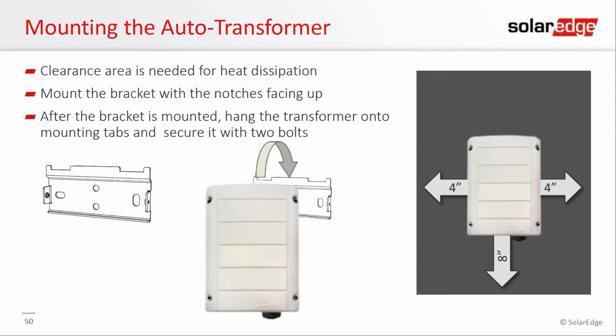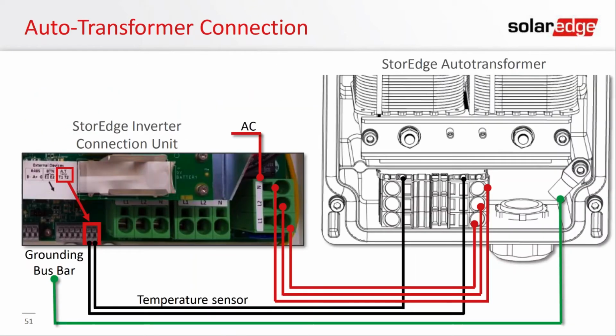You can mount this right next to the inverter. It doesn't need to be far away from the inverter, and it just has cooling clearances of 4 inches on either side. On the inside, there's line 1, line 2, neutral, and ground, as well as 2 temperature sensors, which measure the temperature inside the autotransformer. And I see that is the most commonly forgotten installation step for the autotransformers, installing the temp sensors. They go into this gray terminal block here at the top. It's very easy to miss, and then they route to this gray terminal block inside the StorEdge connection unit.